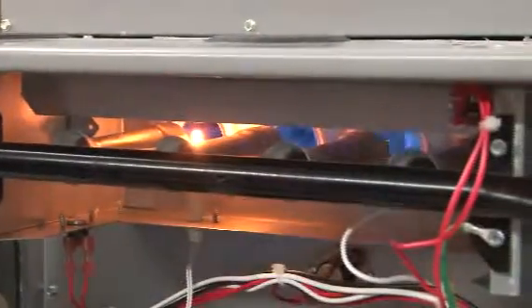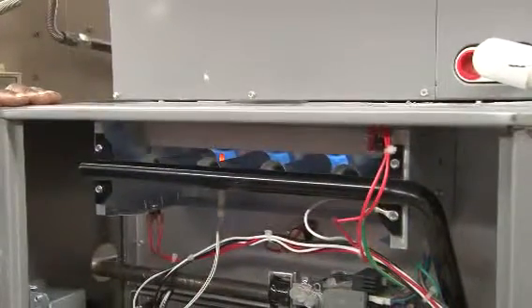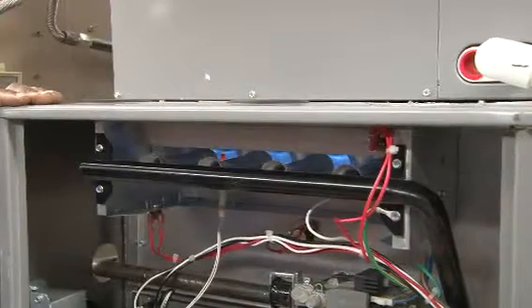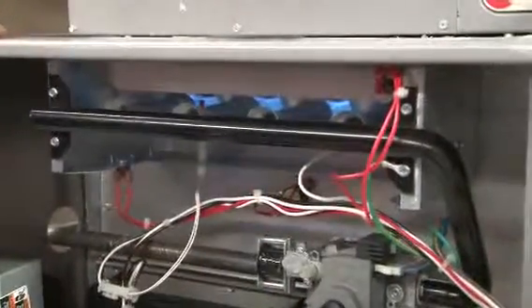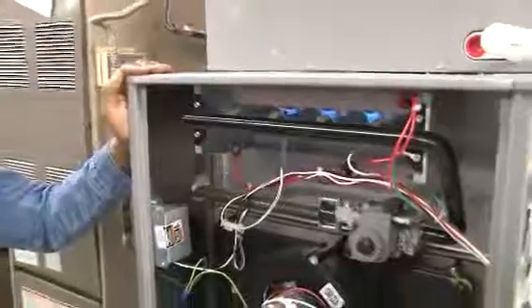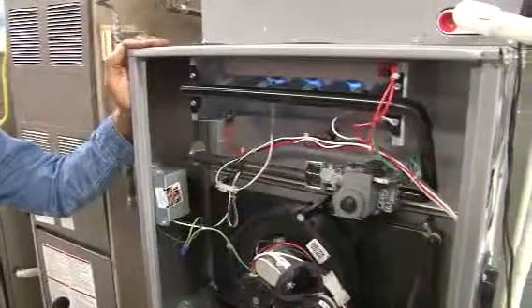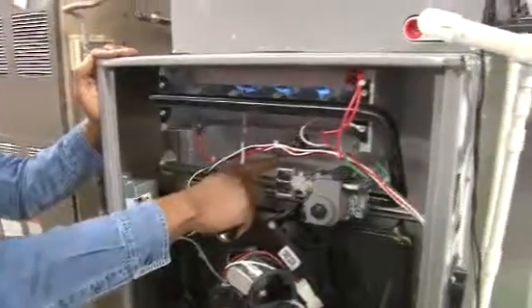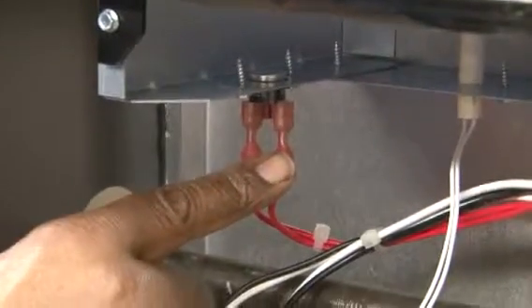Once the burner lights, it will prove that there's a flame by the flame sensor. Now the burners are running. And it's continuing to run because the flame sensor is sensing the flame of the burners. It will continue this way as long as there's airflow through the heat exchanger. There are multiple safety controls, such as a high limit control, a rollout switch, and another rollout switch, designed to protect the furnace in case there's overheat built up inside of the combustion chamber.